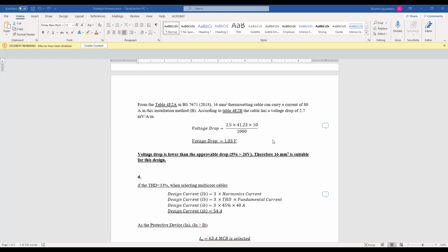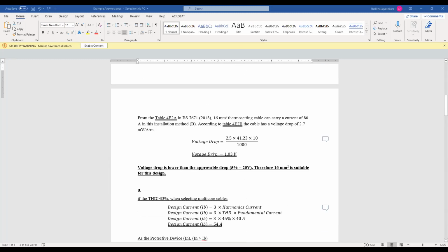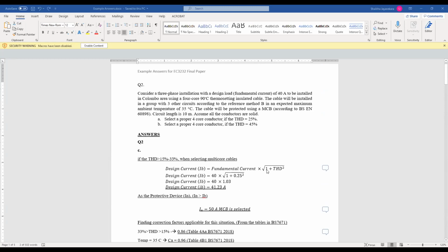So you may remember in our mid semester examination our voltages we took as 230, right? It is only single phase. So if your system is a single phase one, 5% of 230 will be, I think, 11.5, right? So in here it is 20. So even if your voltage drop is higher, you can go to somewhat higher voltage drops here. Okay. So this is how you are going to do the design for a system with third harmonics if the third harmonic level is in between 15 and 33.